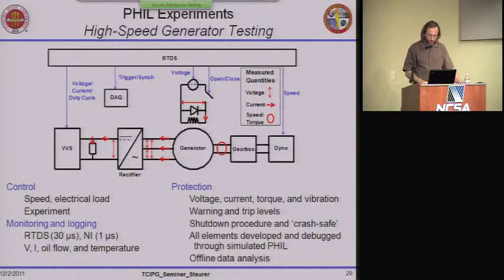We had protection in place - over speed protection, over current protection, exciter over voltage protection, and similar safeguards. That allowed us to very precisely control and protect the experiment in case something didn't work with this first-of-a-kind generator, which spins at 15,000 RPM and must provide a megawatt of power into a controllable DC source/sink. This was very successful and shows you can control experiments like this with a real-time simulator.